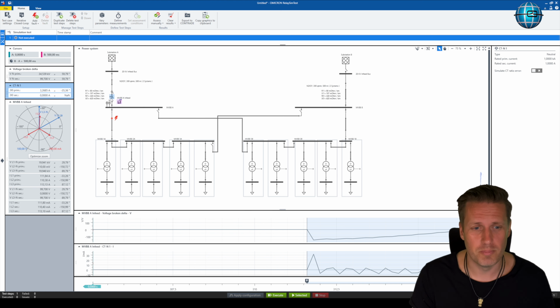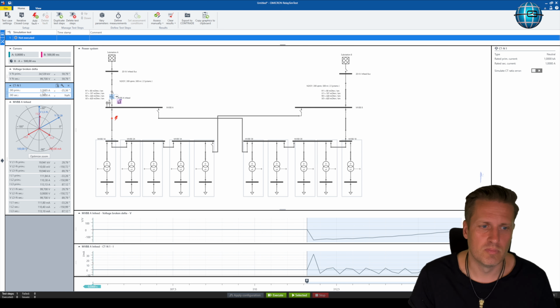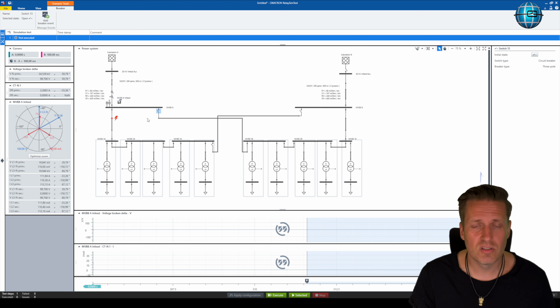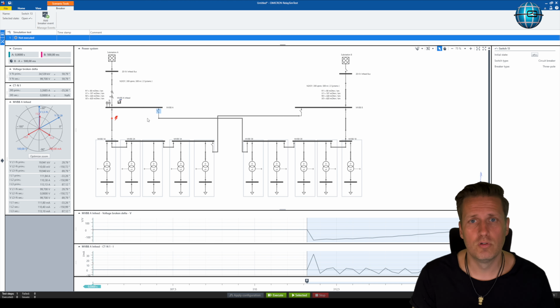So every time a current flows through the split core transformer in two separate directions, it will result in compensation. So the current disappears. So I tell you, if we close this button, nothing will happen, just a little bit. So let's see, we close this button, and as you can see, we almost have the same current here. Okay? And this is the first thing that we have to learn.